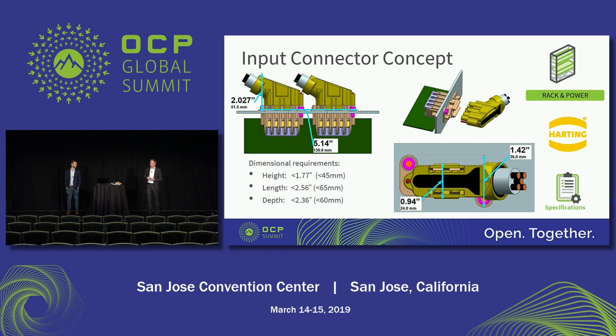touching the male contact. Okay, and I guess the question is, is there a more expensive contact technology that could be used with perhaps a plastic key, so that you could have a family with more ampacity that lived above this one, but higher tech on the contacts? Theoretically, yes, but in the end, from my perspective, the limitation of the connector is then also defined by the cables which you can terminate. So obviously, mechanical-wise, you're reaching a certain limit then, and if you're talking about gauge 7 wires, well, you know what the current ratings are, so that's the limit in the end.